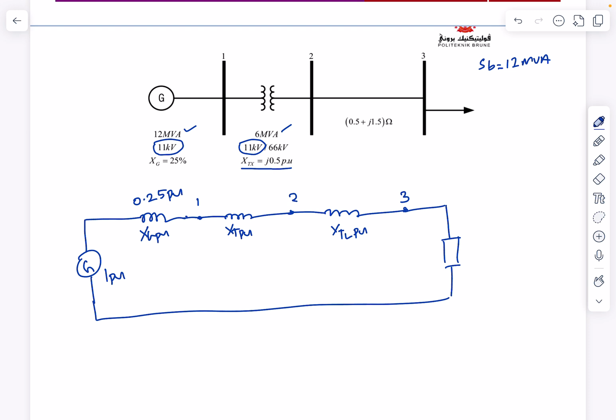For the transformer, its rated MVA is 6 MVA, so we need to convert the transformer's per unit value using the new SB. XT per unit new equals j0.5 times 12 MVA divided by 6 MVA, which equals j1 PU. So we can put j1 PU here.